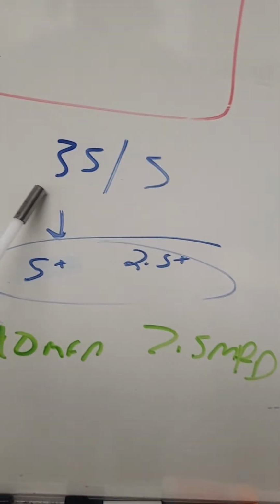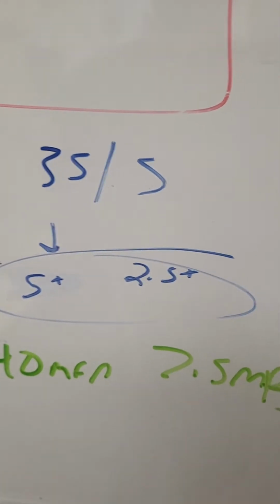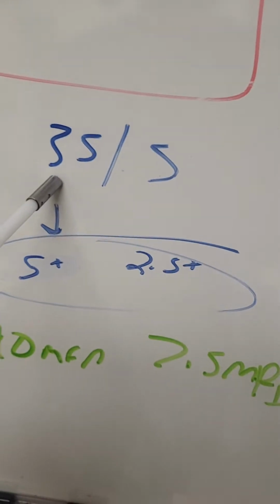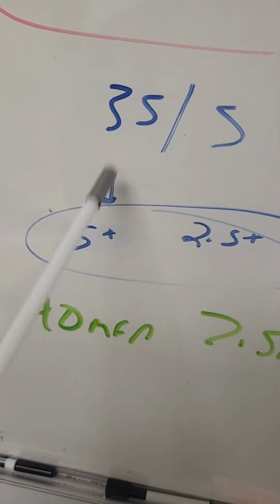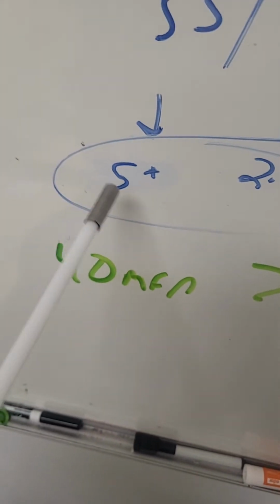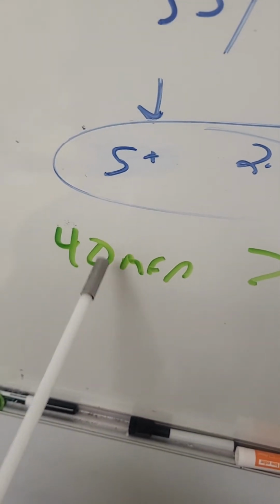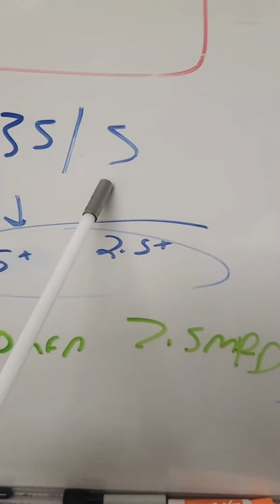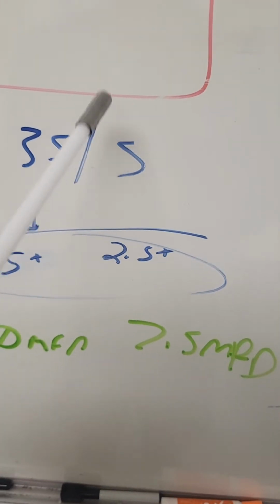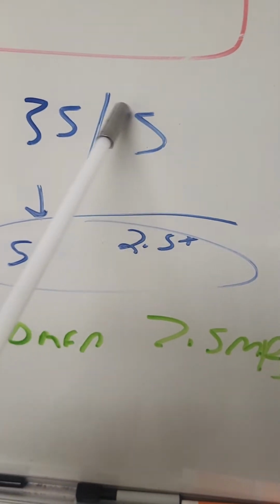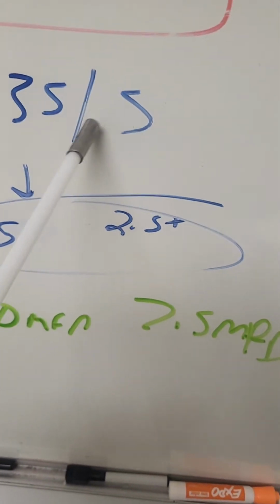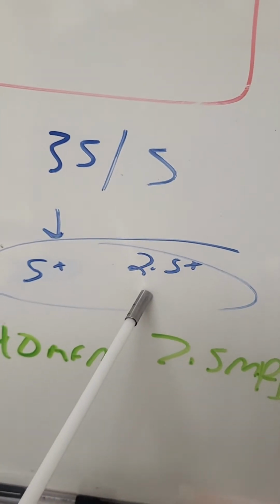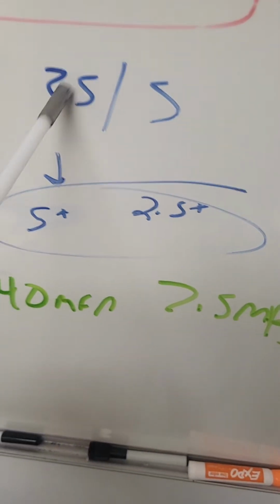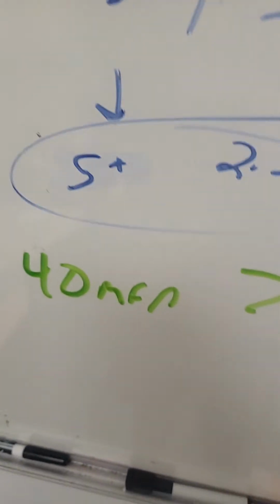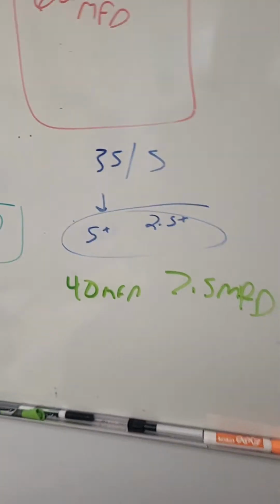Let me break this down. I'm going to give you the parameters. If I got a 35-5 cap, the highest you can go on the compressor side to get a customer up and going is 40 microfarads, and the highest you can go on the fan side is 7.5. So if I got a 35-5, I wouldn't do more than the 35-7.5. The 7.5 can definitely get the fan motor up and going.